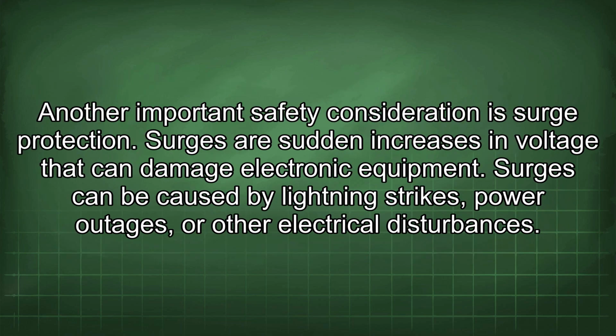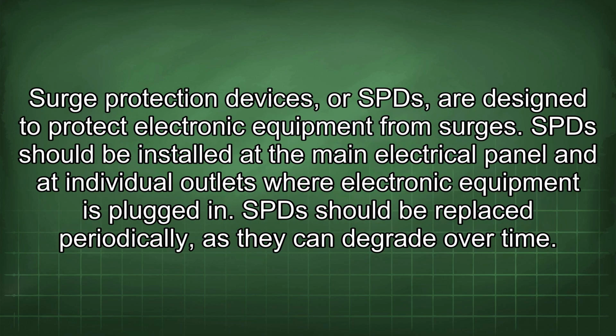Another important safety consideration is surge protection. Surges are sudden increases in voltage that can damage electronic equipment. Surges can be caused by lightning strikes, power outages, or other electrical disturbances. Surge protection devices, or SPDs, are designed to protect electronic equipment from surges. SPDs should be installed at the main electrical panel and at individual outlets where electronic equipment is plugged in. SPDs should be replaced periodically as they can degrade over time.